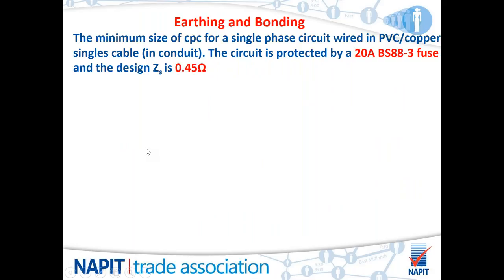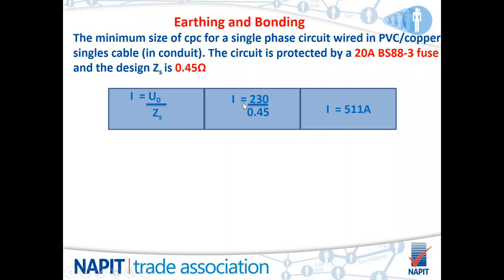Here we have an example of how to work out the sizes of CPCs. Here we've got an example for a single phase circuit wiring PVC copper singles cable enclosed in conduit. The circuit is protected by a 20 amp BS88/3 fuse, and the design ZS is 0.45 ohms. Again, the simple equation for calculating fault current, I equals V over R, essentially. U0 over ZS, put in the 230 volts nominal, your design ZS of 0.45, and your fault current for that circuit would be 511 amps.